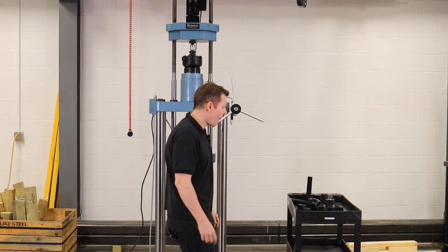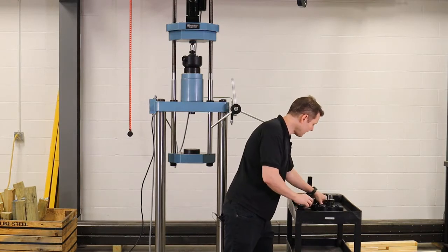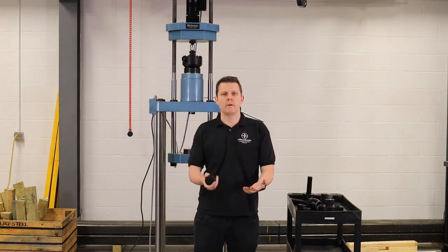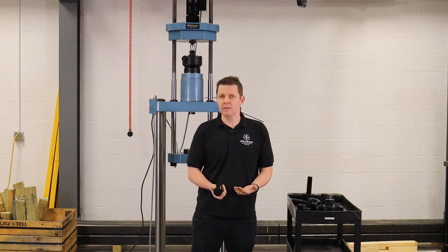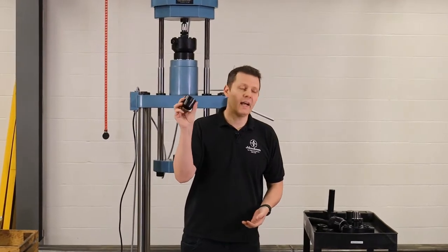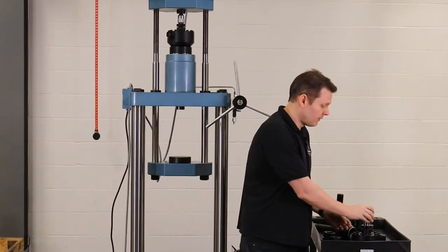We have two options now. If you're wanting to perform a calibration in accordance with ISO 376, we make these CI adapters here. Real simple, they go on the load cell.